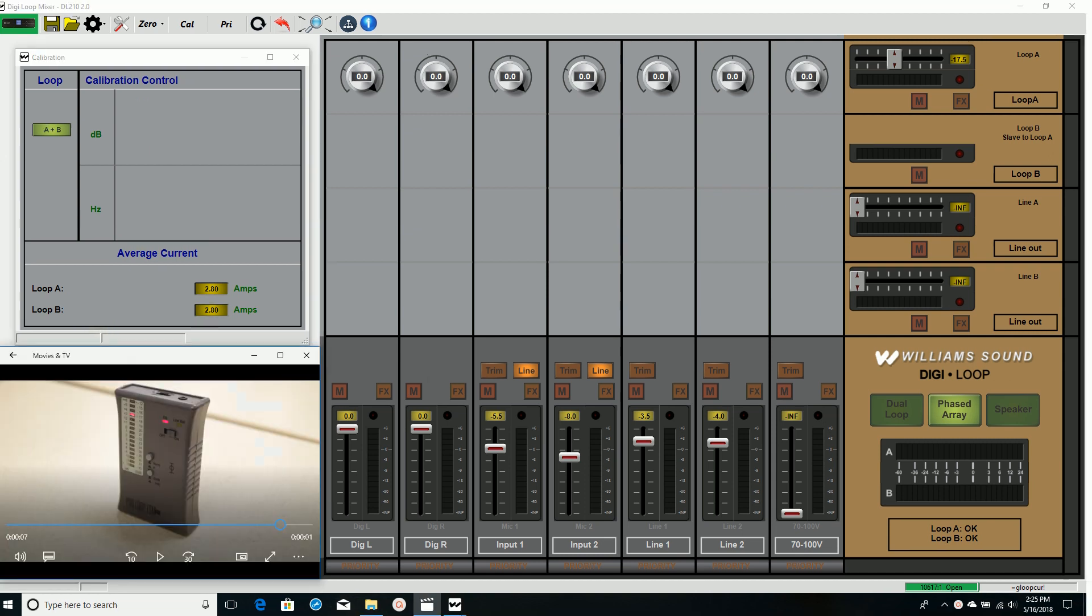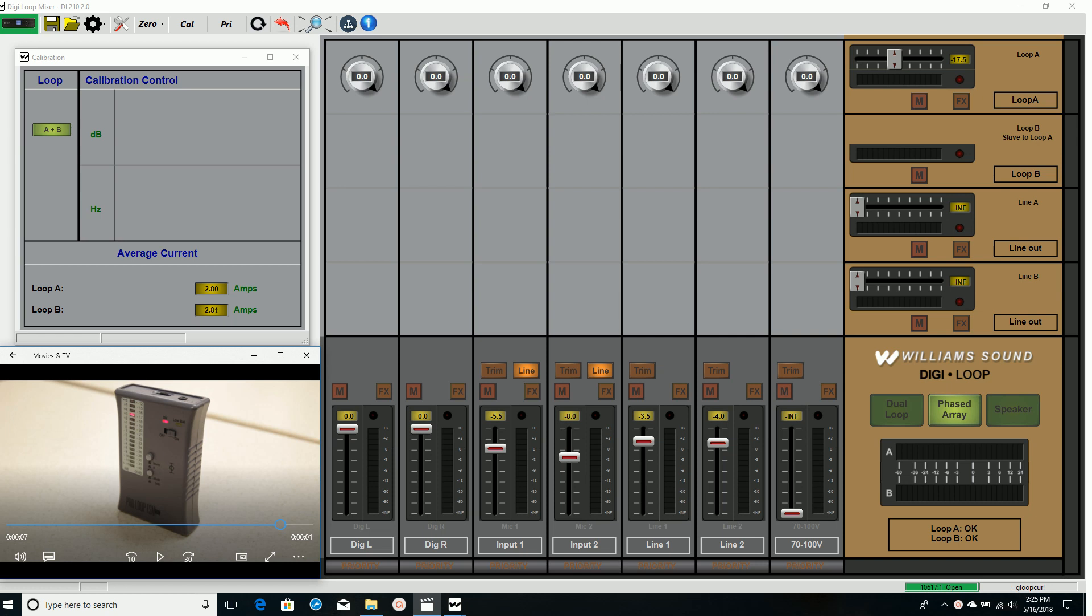As I switch on both loops A and B, we'll likely find that the field strength meter shows 3 dB above 0. I will go back and adjust loop A 3 dB down, no need to reset the offset, and recheck that when A and B are both on, we read 0 dB on the field strength meter.